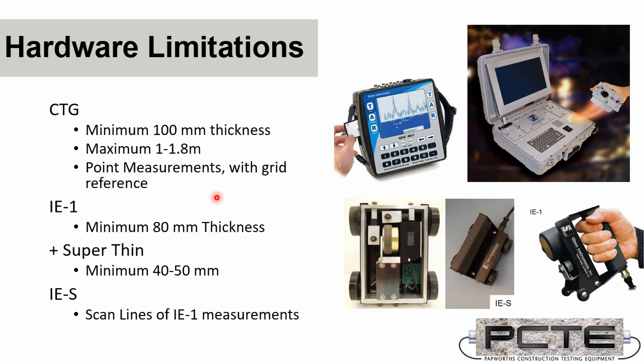The other thing is, for everything except the scanning systems, impact echo is a point measurement. So if you want to measure an entire slab, you'd work over a grid reference. And there is features in the software to make it easy to collect that grid and to output it for future charting.